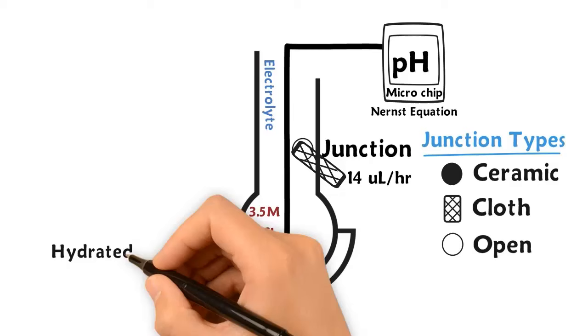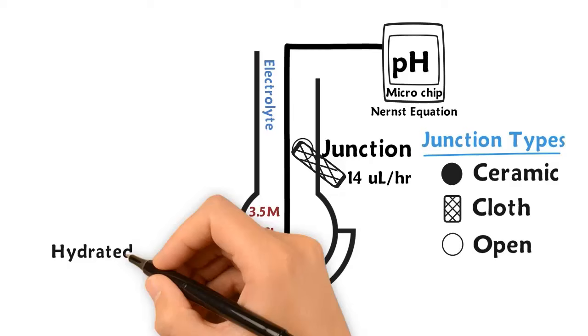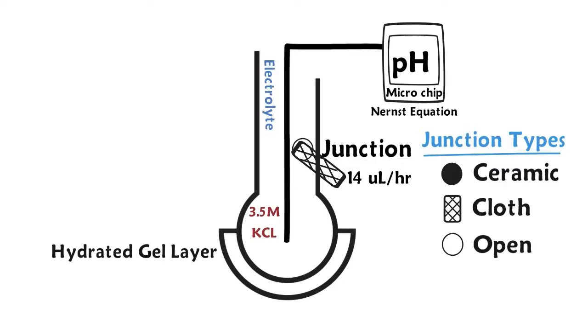On the bottom layer of the glass bulb, you have a gel layer that must be hydrated for proper use. You will have your glass bulb submerged in a testing or storage solution that will submerge the junction.